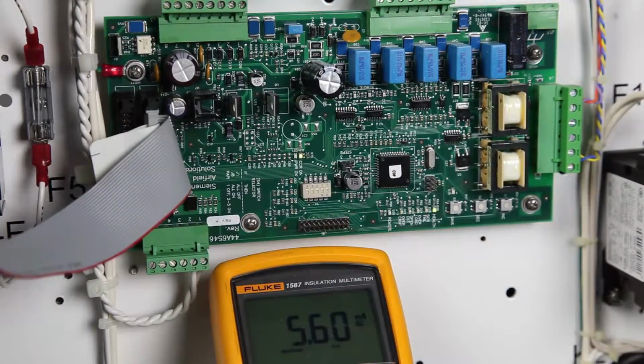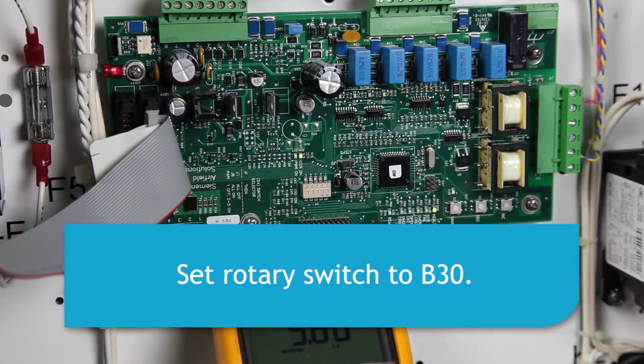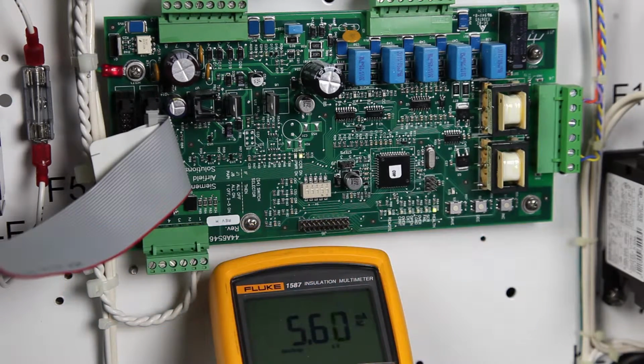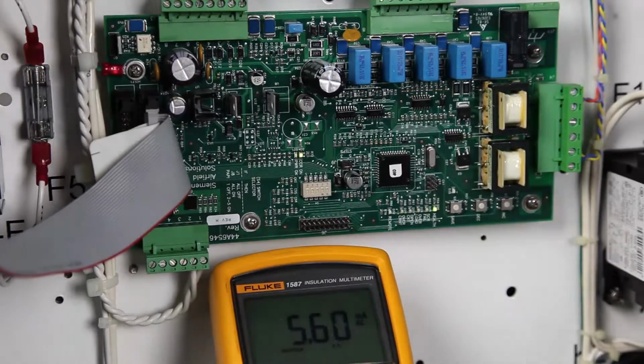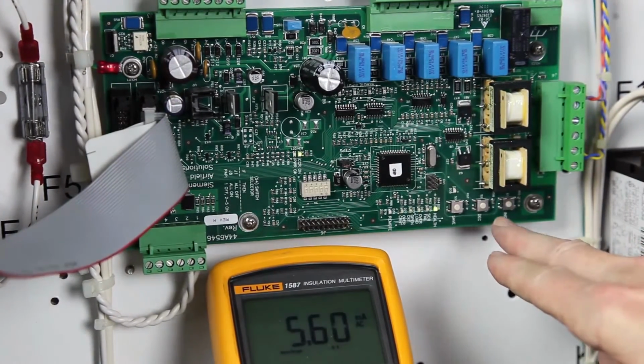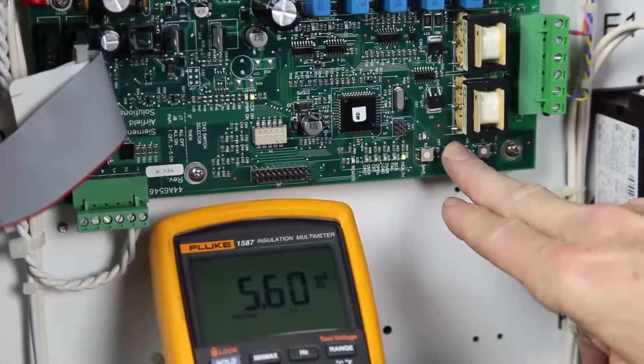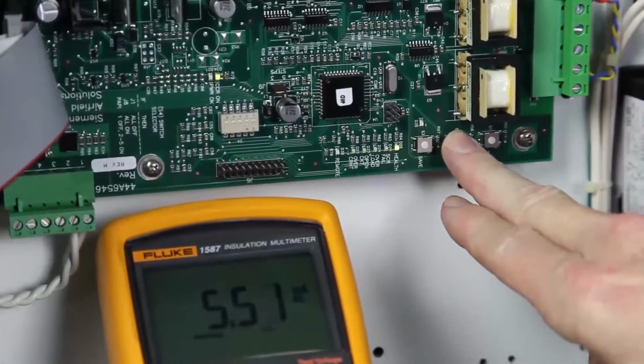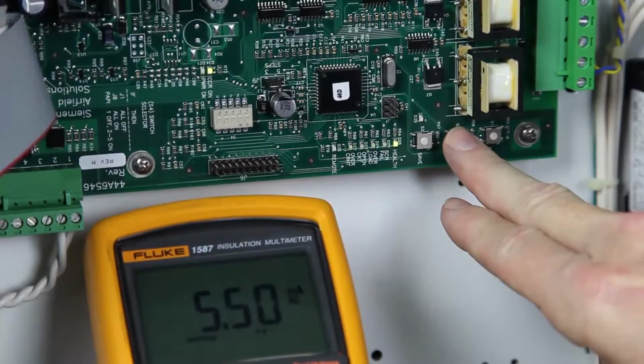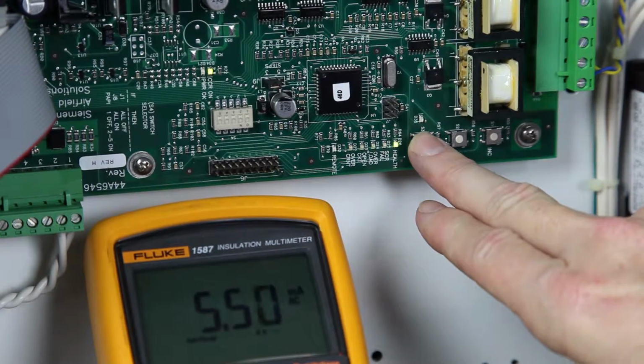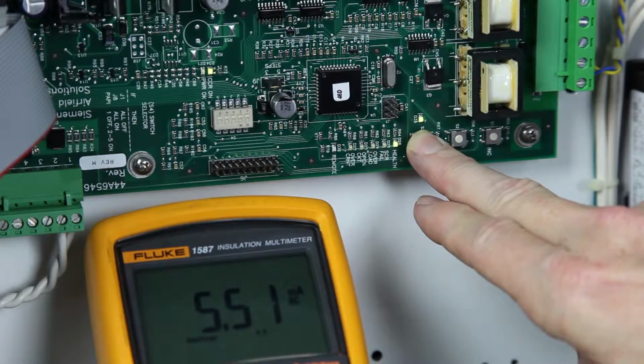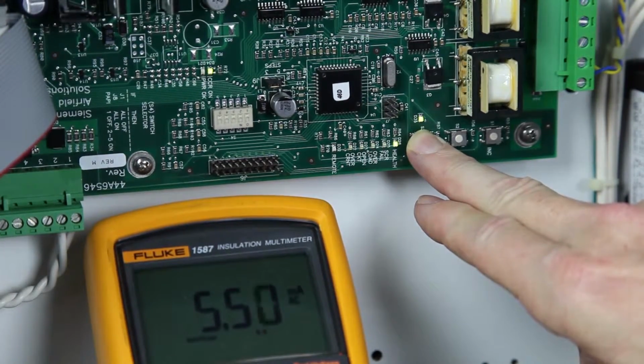So now we want to adjust the remaining steps for a 3-step 6.6 amp CCR. Using the local control switch, we will set it to the B30 setting and we want the output current to be 5.5 amps. As we can see here, the current setting is a little bit high, so what we want to do now is hit the decrease button and get it to 5.5 amps and press and hold save for 2 seconds and ensure the LED is on.